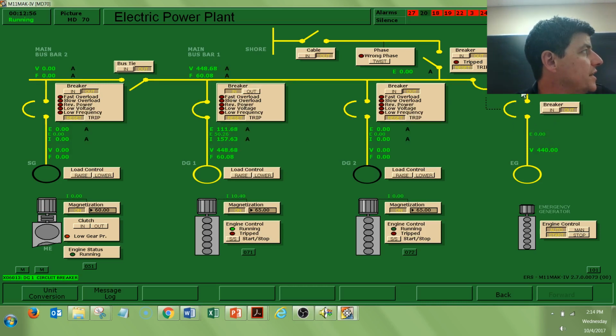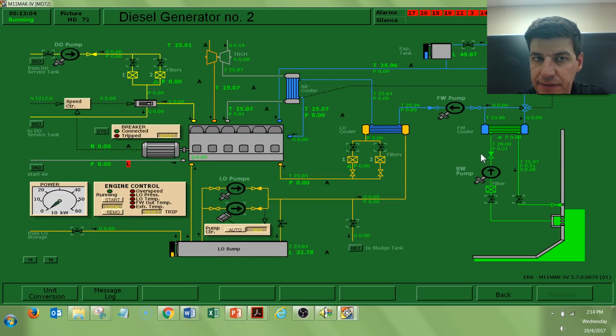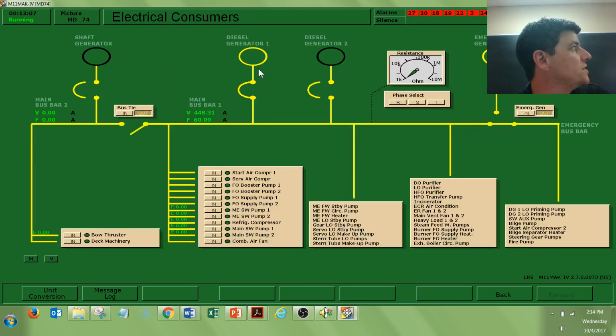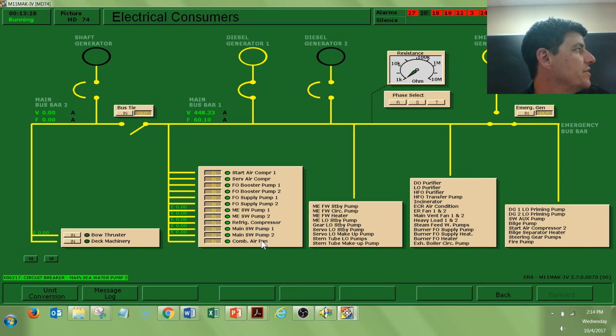Our emergency generator disconnects and eventually will turn itself off after not being needed for a little bit. On the electrical consumer side, diesel generator now supplies to all of my banks. Inside of these, I need to engage a breaker in order to allow any of these guys to function. I'll turn them all on, but really the ones that we're going to need would be our combustion air fan on the boiler, so the air blower on the boiler. Some of our air compressors are going to be our main components.